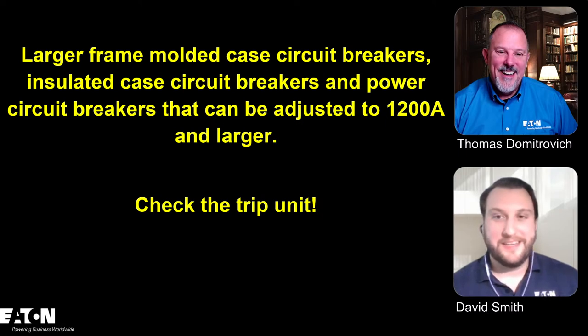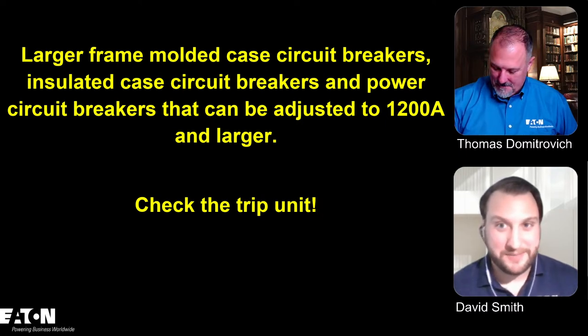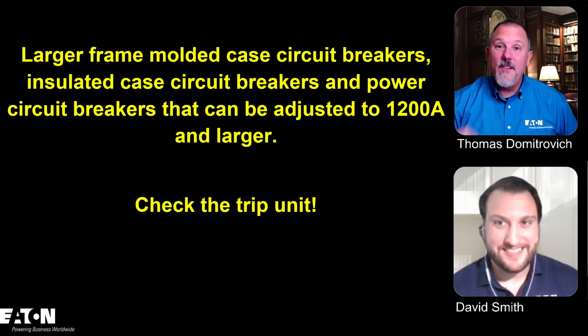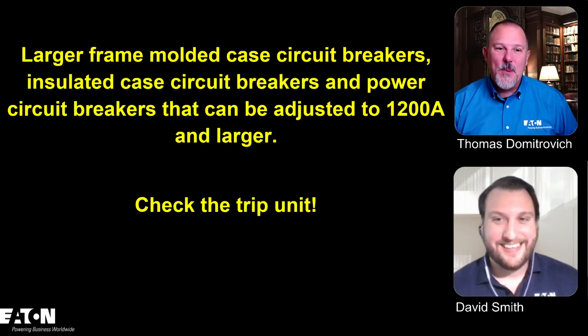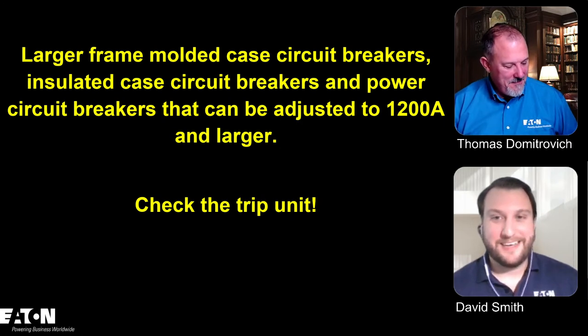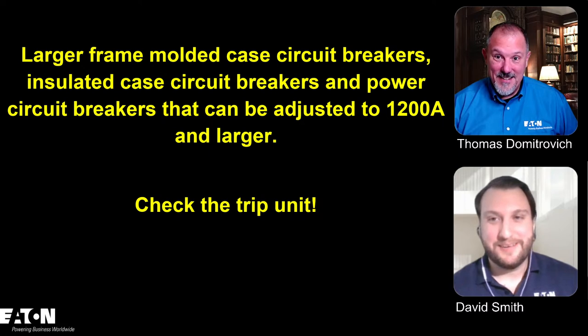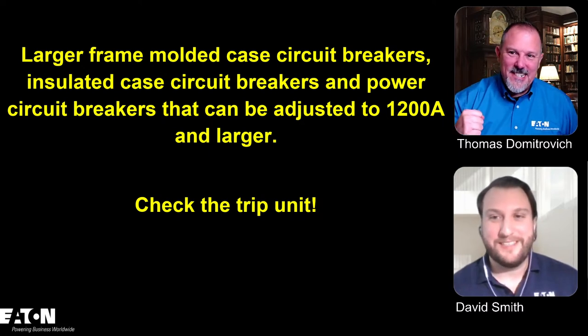Does it say... Is it over 1,200 amps? Is it 1,200 amps? It's over 1,200 amps. It's a medium voltage breaker. I would say if it's a circuit breaker and it can be adjusted or rated to 1,200 amps or above, then you would need some type of arc energy reduction.